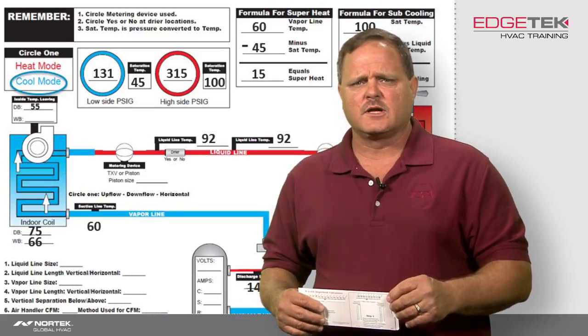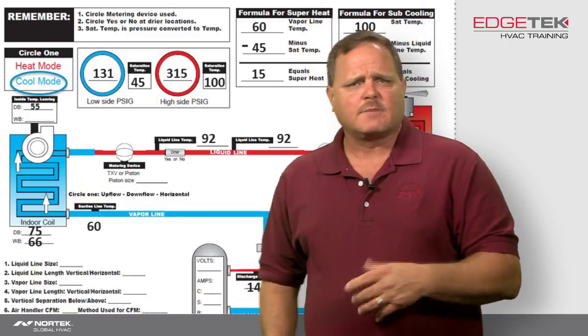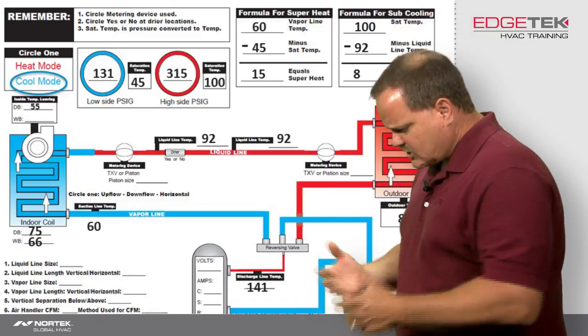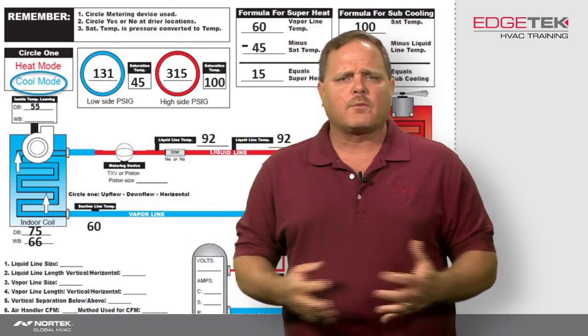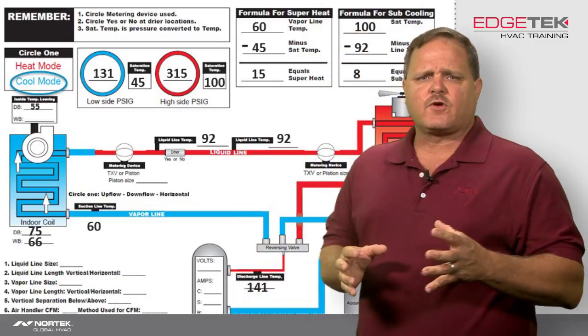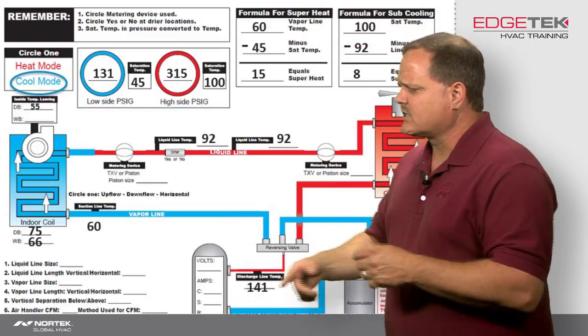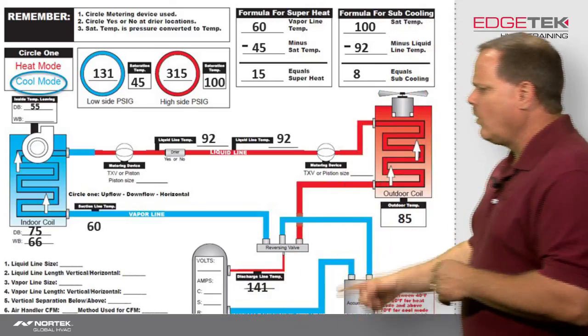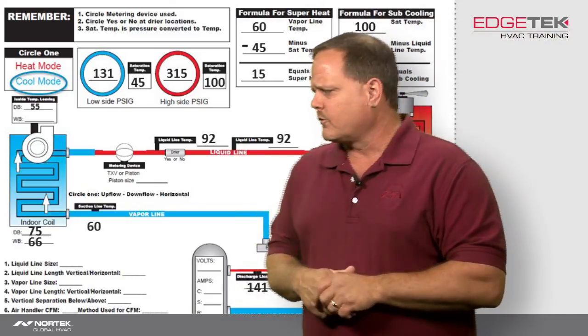Once you know what that required superheat is, we can move on to using these job checkout sheets to determine what's going on with the system. For this first example, this is a normal operating system, and our load conditions for all the examples I'm going to give you here are not going to change. We're going to keep a 66 degree wet bulb temperature entering the evaporator and hold an 85 degree outdoor temperature through all the examples.